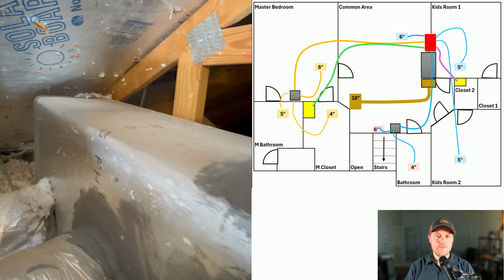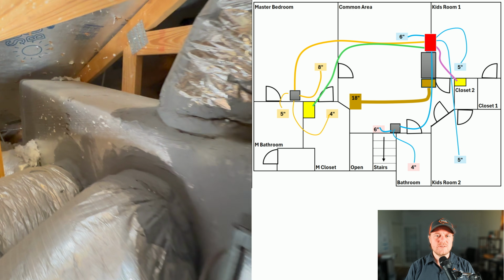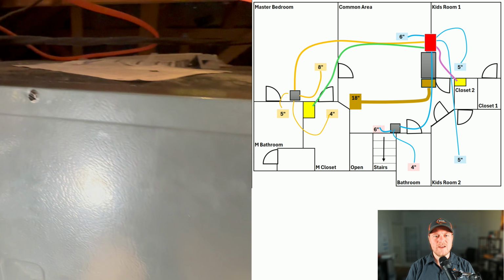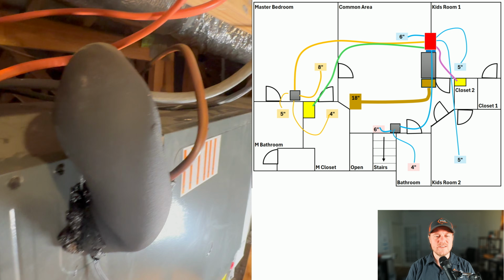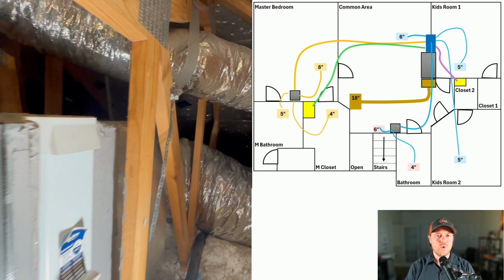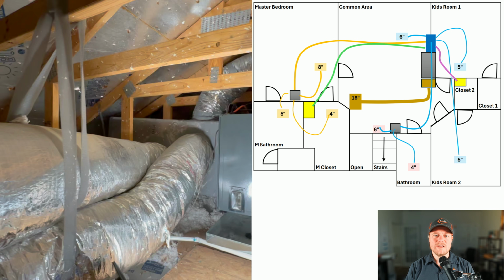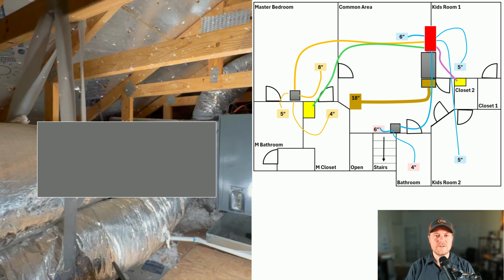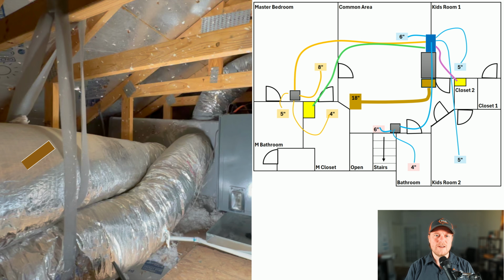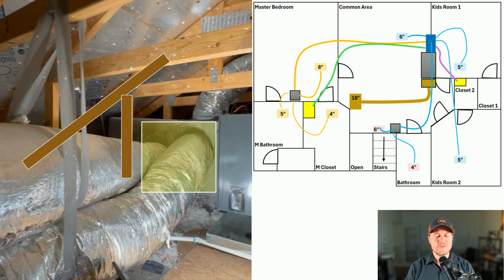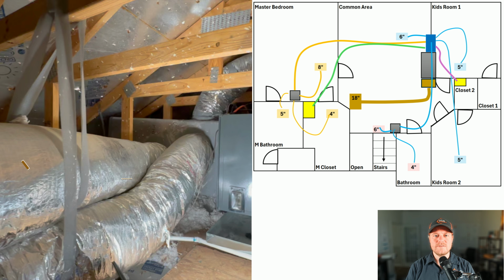However, I'm running into a problem with the supply plenum. We know that we have to push the ducts around 18 inches away from the air handler to make sure that everything pressurizes equally. That way one duct doesn't push more air than another one does. And I'm really needing a 4-foot supply plenum to make that happen. That way I have enough room to push the supply ducts far enough back. However, there's a roof line in the way, and right beside everything is framing. This is why they put the ducts so close to the air handler, because there's just nowhere else to put it. And I can't move the air handler anywhere else because there's no other good spot. So basically, since the attic is so small, I'm very limited on my options here.